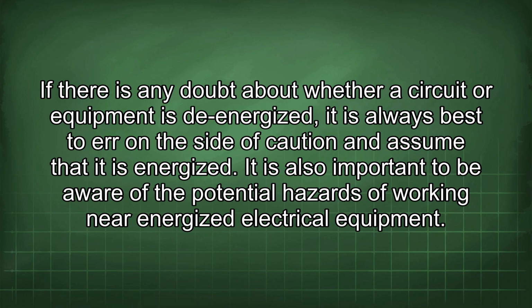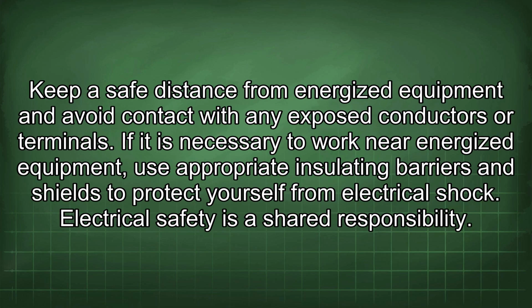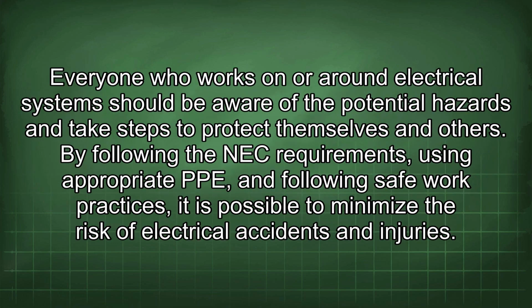It is also important to be aware of the potential hazards of working near energized electrical equipment. Keep a safe distance from energized equipment and avoid contact with any exposed conductors or terminals. If it is necessary to work near energized equipment, use appropriate insulating barriers and shields to protect yourself from electrical shock. Electrical safety is a shared responsibility. Everyone who works on or around electrical systems should be aware of the potential hazards and take steps to protect themselves and others. By following the NEC requirements, using appropriate PPE, and following safe work practices, it is possible to minimize the risk of electrical accidents and injuries.